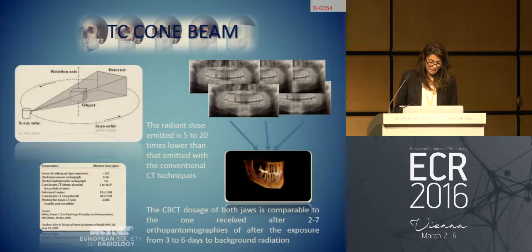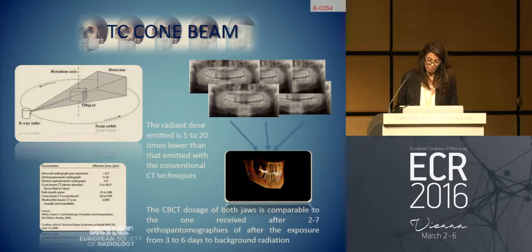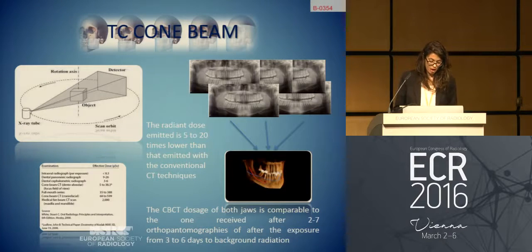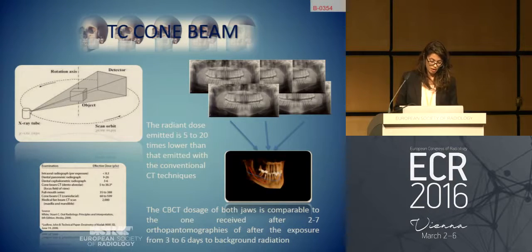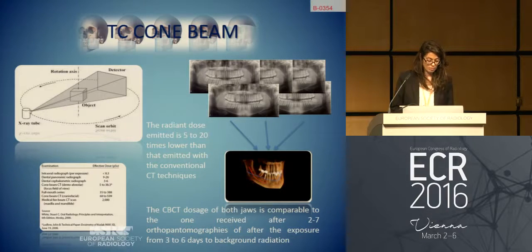Compared to the normal multi-layer CT, the cone-beam technique allows the pulse emission of radiant beams in just one rotation of the detector tube, using an X-ray beam with conical morphology and a single detector — flat panel or brilliance intensifier. The machine is also characterized by low weight, standard power, and lower cost. The radiant dose emitted is 5 to 20 times lower than with conventional CT, also due to the shorter duration of exposure. The examination of both jaws with cone-beam CT has a very small dosage, comparable to two to seven orthopantomographies or three to six days of background radiation exposure.